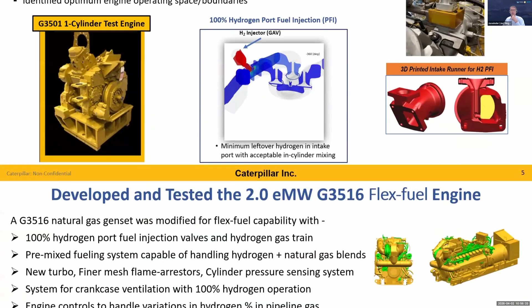As I said earlier, we took our existing production natural gas 16-cylinder G3516 genset and converted it into a fuel-flexible genset. Some of the additional changes we made include a 100% hydrogen port fuel injection system. We use port fuel injection for injecting hydrogen in individual cylinders. Natural gas is pre-mixed, so it's injected pre-turbo, not in every single cylinder, whereas hydrogen is injected in individual cylinders.